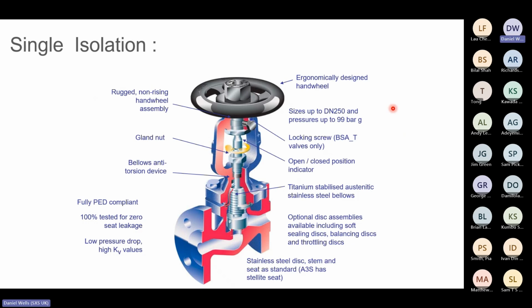So isolation is also critically important with steam systems. We never really want to see a quarter turn valve used on a steam system for two reasons. For example, a ball valve or a butterfly valve, they operate very, very quickly. And the problem that can cause is if we've got any trapped condensate, it's really going to result in a likelihood of water hammer taking place. Opening that valve very quickly, we're going to get a huge pressure drop and we're going to get that knocking, banging, that violent vibration as a result of that water hammer.